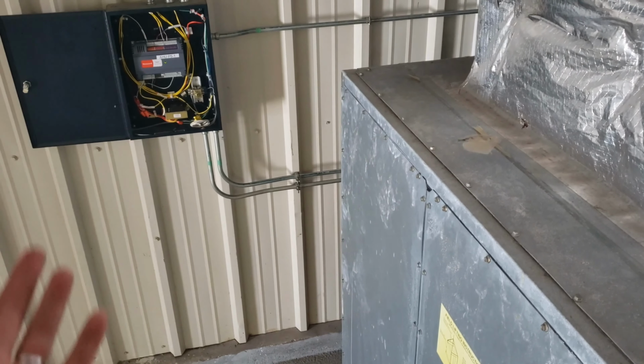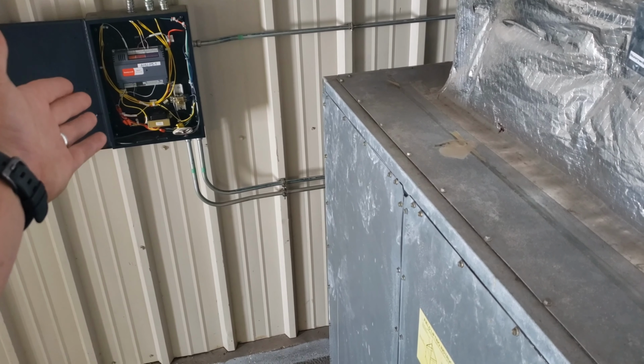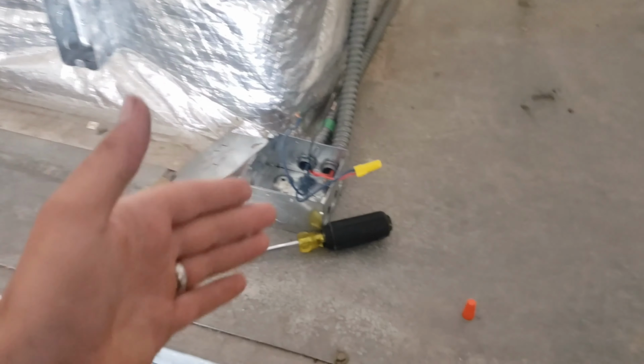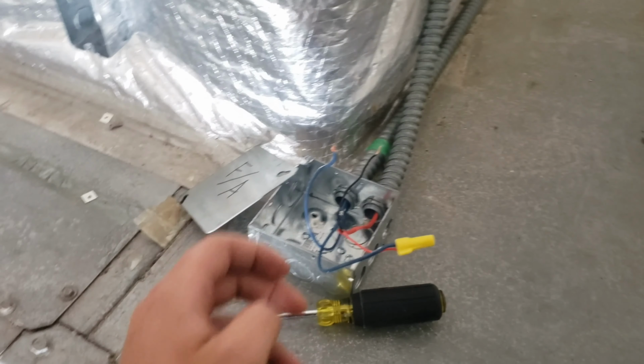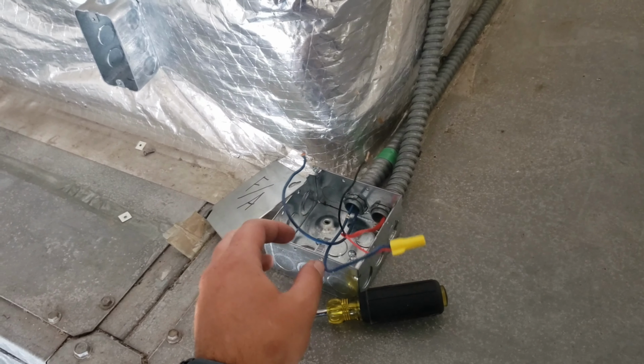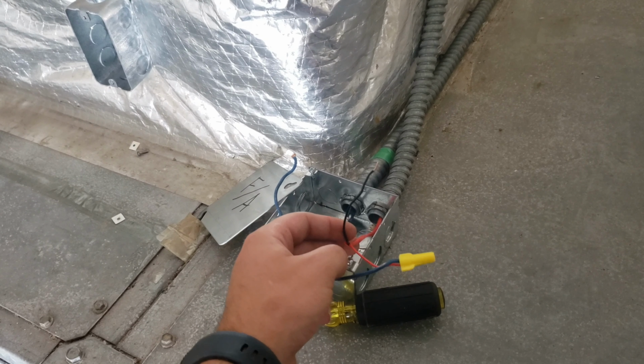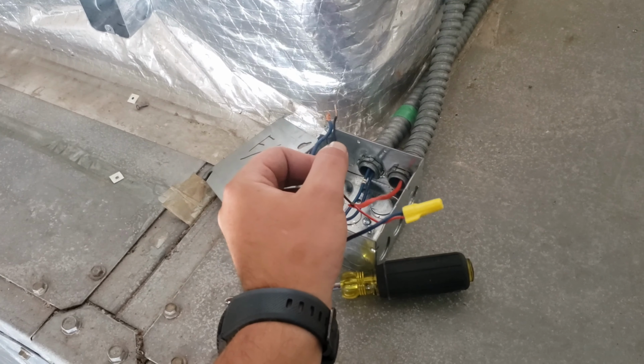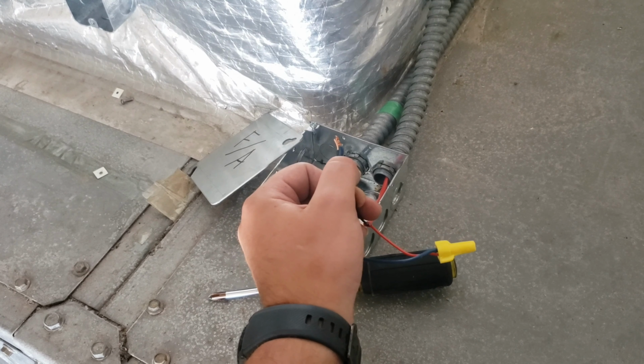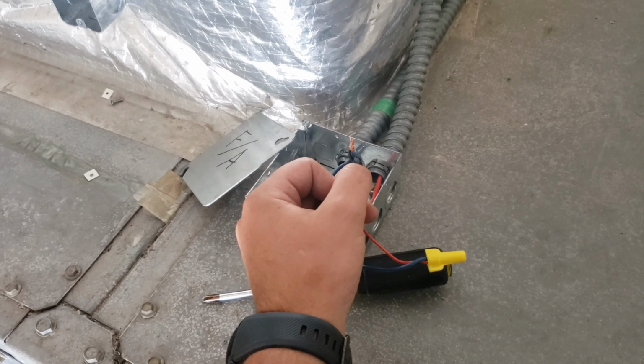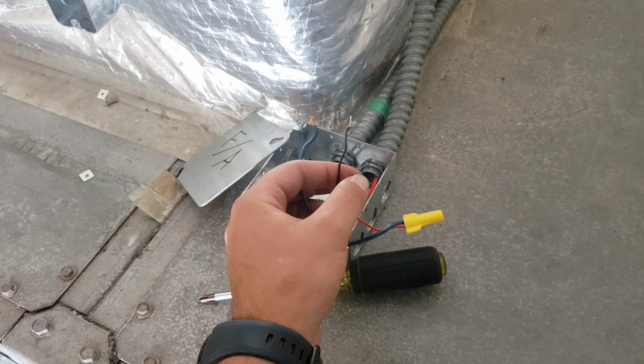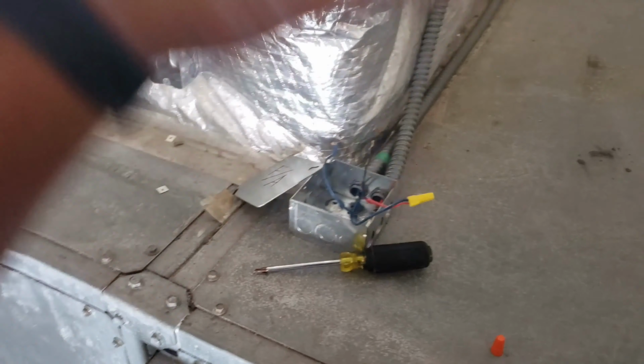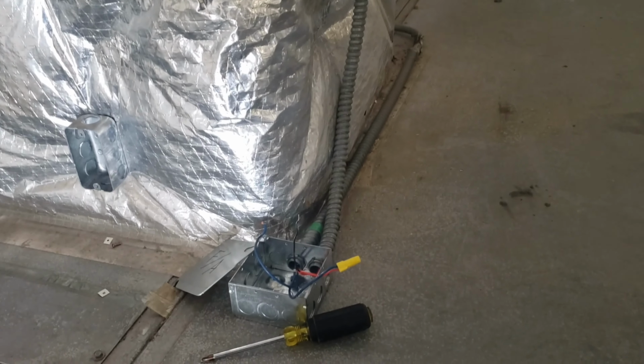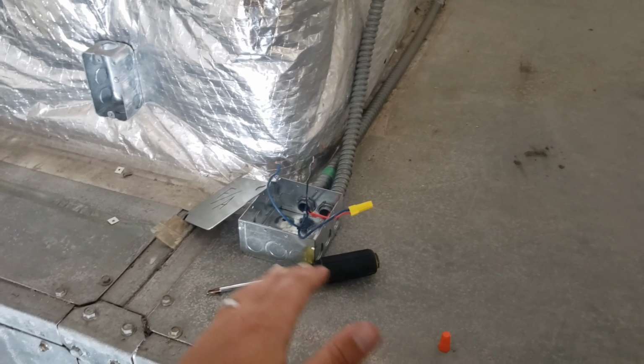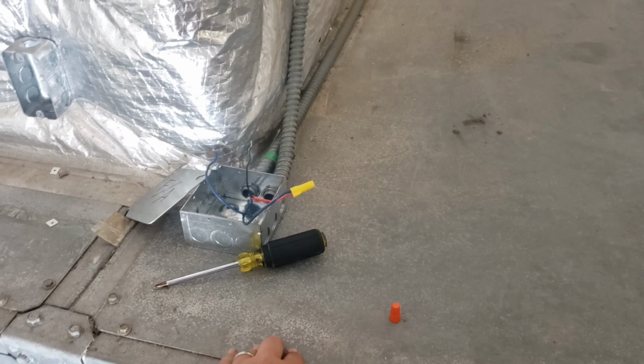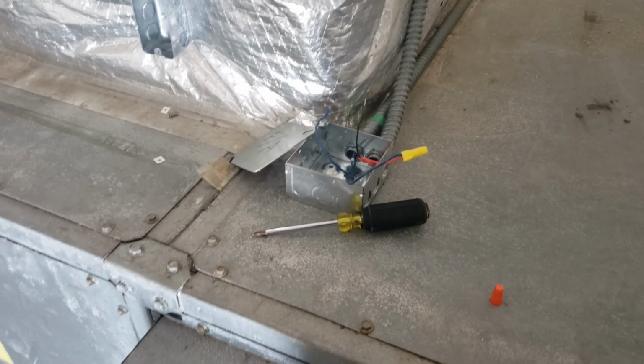Alright, and so I found it. So what I'm doing, your automation's calling for it. I trace out the fire shutdown circuit on the controls, and this is where it came to. These two blue wires are from the automation, there's red wires from the fire detectors. And that's what I'm looking for right there. So if this fire system trips, I know that's going to shut down. What this tells me is this unit wasn't working because of the fuses blown in the starter panel.